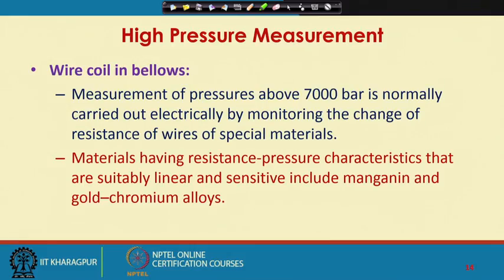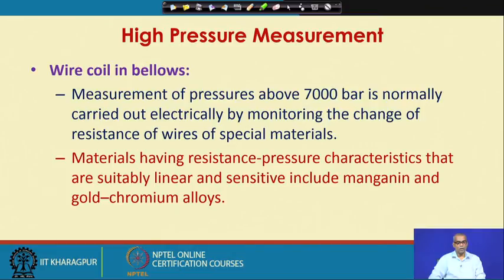That completes our discussion on moderate pressure measuring instruments. We will now talk about electrical high pressure measuring instruments. High pressure measurement uses a coil in bellows. So, it makes use of an electrical coil in bellows. Measurement of pressures above 7000 bar is normally carried out electrically by monitoring the change of resistance of wires of special materials. Materials having resistance pressure characteristics that are suitably linear or nearly linear and sensitive include manganin and gold chromium alloys.